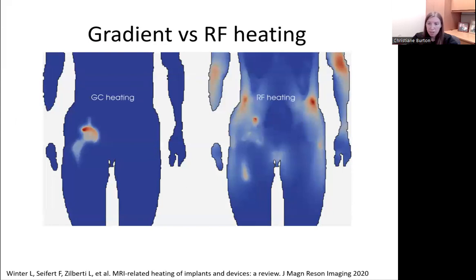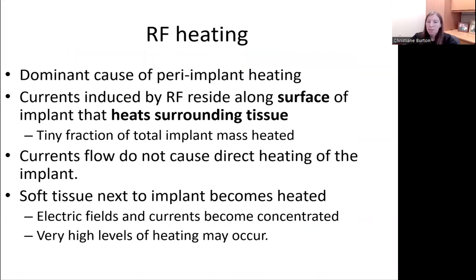This is a simulation of gradient coil versus radiofrequency heating in an adult with a unilateral hip prosthesis. In this case, gradient heating is confined to the immediate vicinity of the implant and greatest in the extended cross-section of the acetabular cup. RF heating can create hotspots throughout the body. RF heating near the implant is most prominent at pointed elements, that being the tip of the femoral stem and the screw in the acetabulum, in the superior acetabulum. RF-related heating is the dominant cause of heating around an implant.